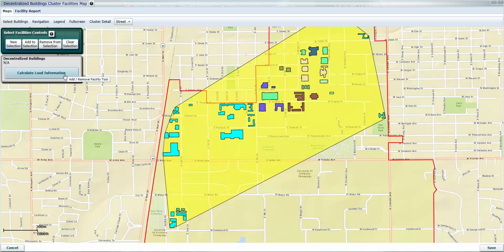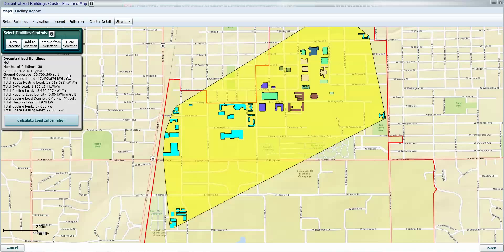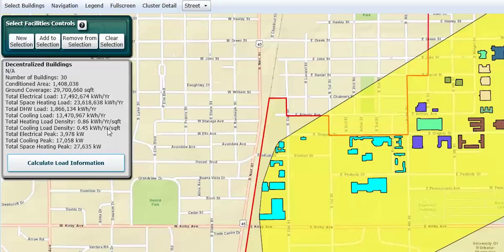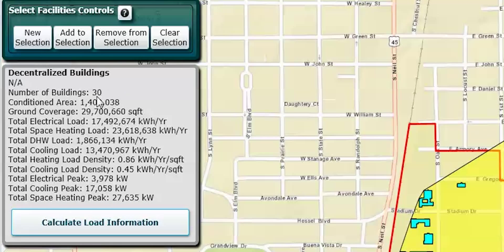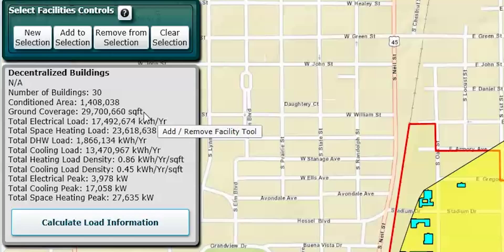Now if we want to, we can click 'calculate load information' and we'll have some information related to those buildings. This is being brought forward from the facilities information, rolled up for all the buildings, and then displayed here. So we can determine the number of buildings, the amount of conditioned area in square footage, and the ground coverage area — related to the yellow shape you can see here. That kind of information is useful when determining whether or not a central system would make sense.